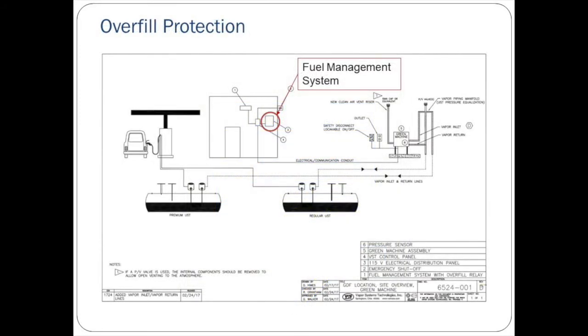Overfill protection. The Green Machine uses a dry vacuum pump to control pressure in the underground storage tanks. This pump is sensitive to liquid and can be destroyed if liquid fuel makes its way into the pump. So it is important that the Green Machine and the VST control panel be made aware when there is an overfill related to a fuel delivery.